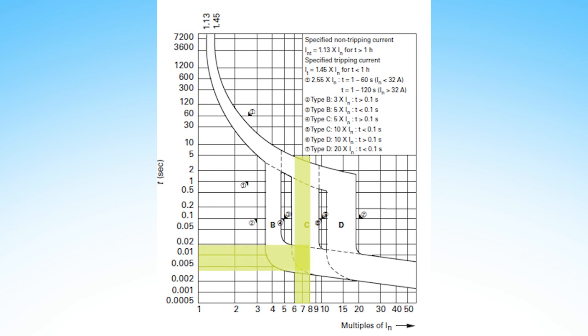We can see on a B or C curve this amount of current would trip the breaker in well under 0.01 seconds. This would not be enough time for a motor to start and the current to come down, but on the D curve this gives us at least one second, which should be plenty of time for the inrush to subside.